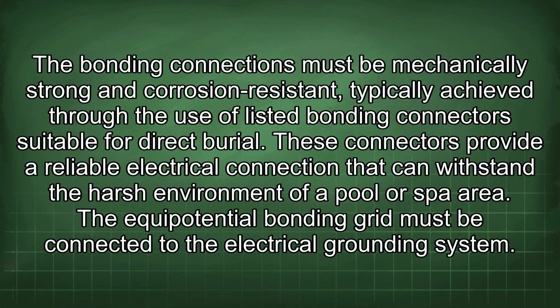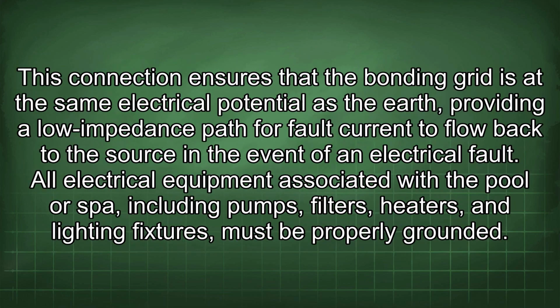The equipotential bonding grid must be connected to the electrical grounding system. This connection ensures that the bonding grid is at the same electrical potential as the earth, providing a low impedance path for fault current to flow back to the source in the event of an electrical fault.